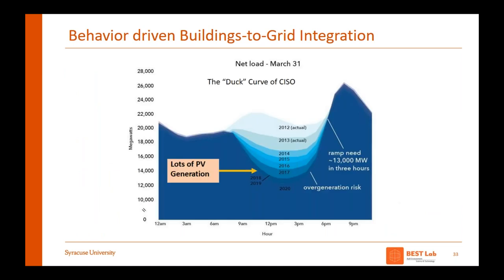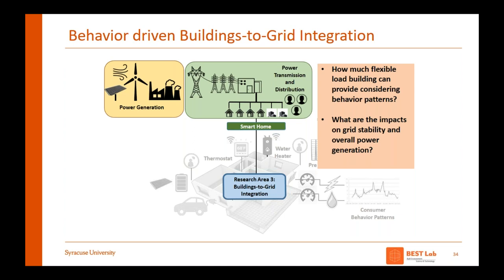If the grid has an over-generation risk, as a building responding to the grid, I can control HVAC to dump cooling energy into rooms that aren't occupied, without sacrificing people's comfort, to provide the grid more load and avoid over-generation risk. Or if the grid ramps up quickly and says it doesn't have the capacity to ramp up 13,000 megawatts in 3 hours, can the building help? Yes. I can elevate the temperature in unoccupied rooms in summer, reducing HVAC load without sacrificing comfort, since no one is in the room. So the building can respond very quickly.